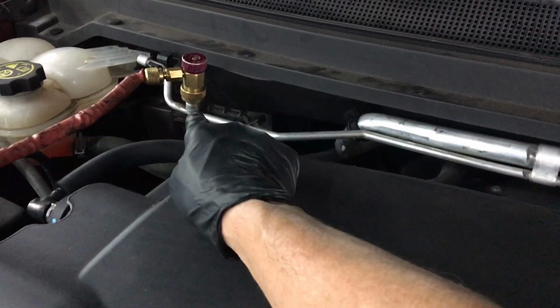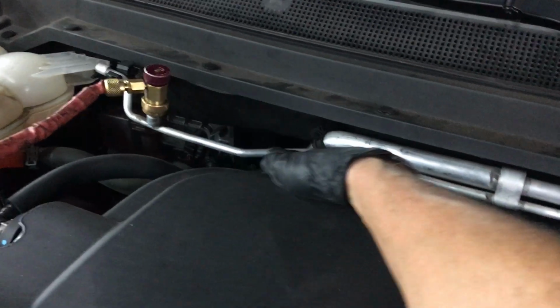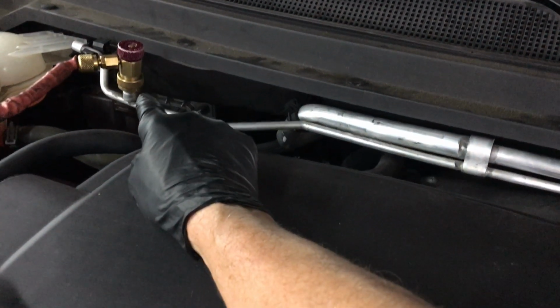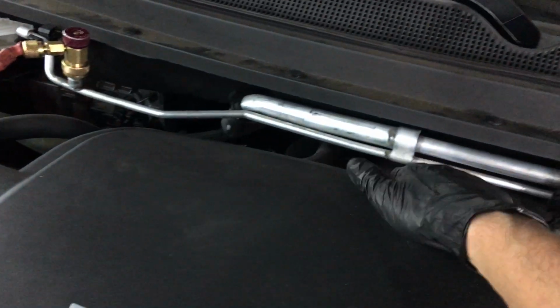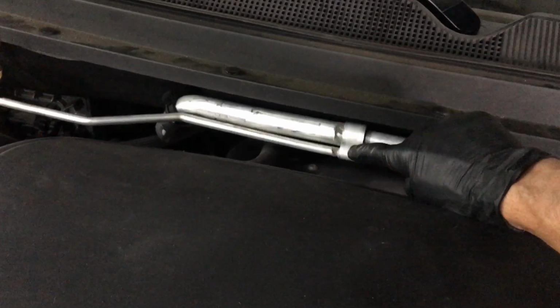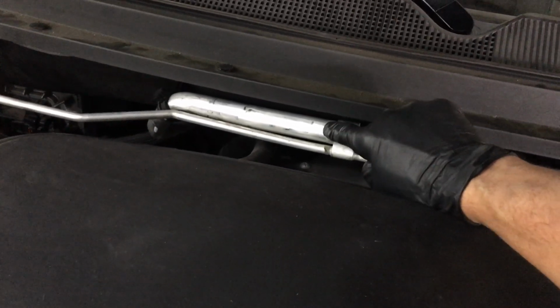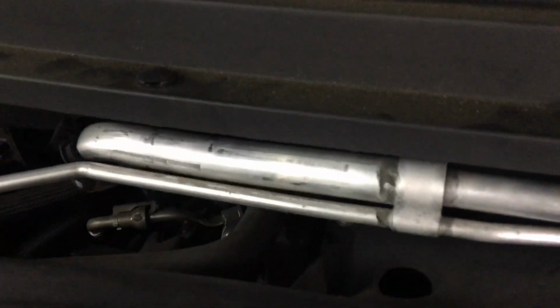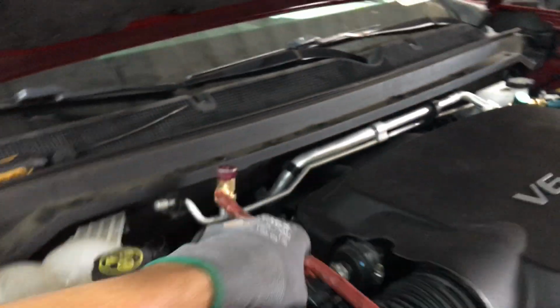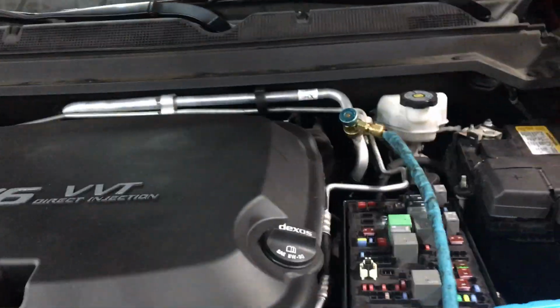And our high side gauge in this line is actually not connected to the system other than reading pressure from that point to here. This has nothing to do with the flow of refrigerant. All it is is a port to draw vacuum and read pressure. That is all. It has nothing to do with flow. The flow is actually going from here, going inside this fitting. This valve is drilled out and ported. It's going around a bunch of little tubes. And if you actually look really, really carefully at this tube, you can actually see little squared off sections. Those are like little ports that the liquid is traveling in. The liquid is traveling inside. And let's see if we could see it on the other side. And we cannot see where the liquid line exits and goes into the expansion valve.